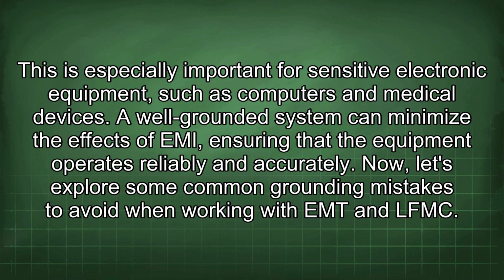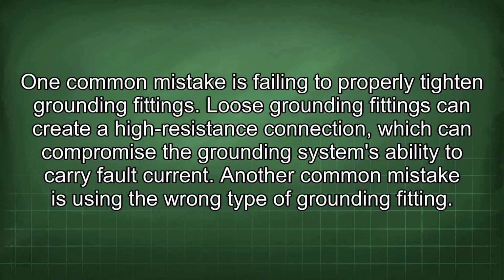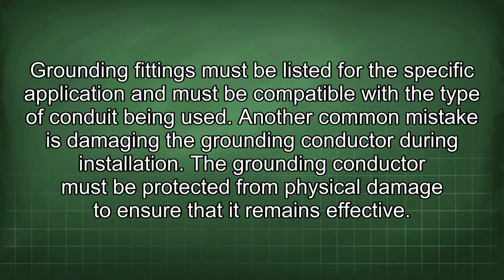Now, let's explore some common grounding mistakes to avoid when working with EMT and LFMC. One common mistake is failing to properly tighten grounding fittings. Loose grounding fittings can create a high resistance connection, which can compromise the grounding system's ability to carry fault current. Another common mistake is using the wrong type of grounding fitting. Grounding fittings must be listed for the specific application and must be compatible with the type of conduit being used. Another common mistake is damaging the grounding conductor during installation. The grounding conductor must be protected from physical damage to ensure that it remains effective.